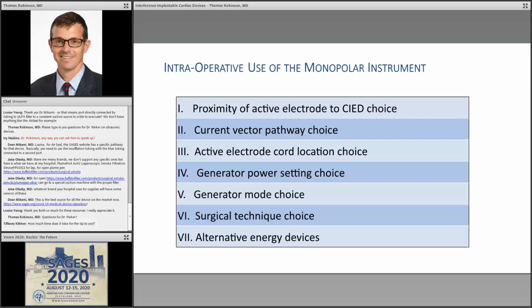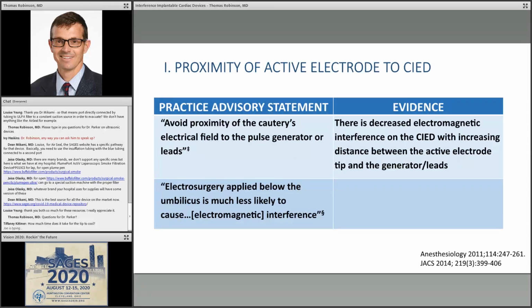And this is what you can actually do in the operating room. You as a surgeon, what you can do to reduce the chances that your monopolar instrument or the bovie will interfere with the implanted cardiac device. And so these are the variables that are associated with disruption of your cardiac implanted device. So we're just going to go down and march down them in order. We're going to start with the proximity of the active electrodes, that's your monopolar pencil, to the device. And so the practice advisories state you should avoid proximity of the cautery, and what they're talking about is the electrosurgery tool, electrical field to the pulse generator or the lead, so that's the cardiac implanted device.